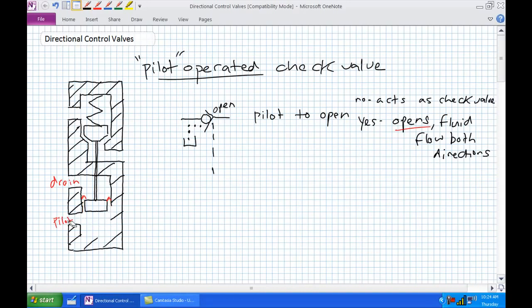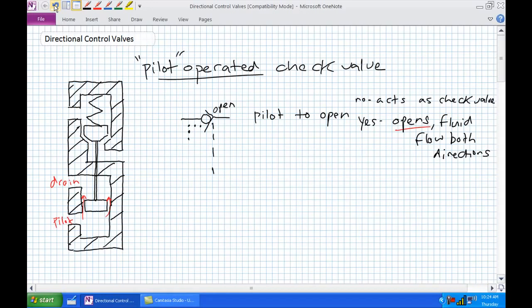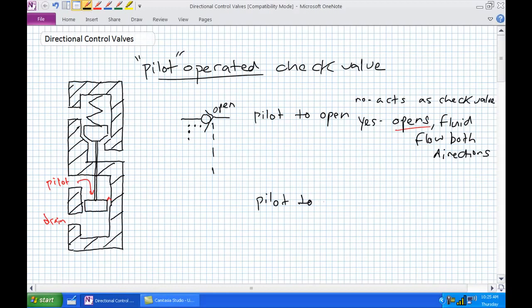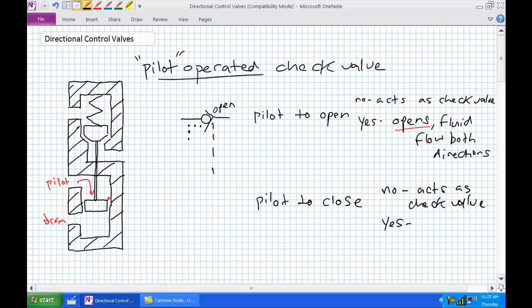If we reverse the pilot and drain connections, we've created a pilot-to-close check valve. Now the pilot pressure is actuating from the other side, holding the poppet down. With no pilot pressure, it acts as a check valve just like normal. If there is pilot pressure, a pilot-to-close closes — no fluid flow in either direction.